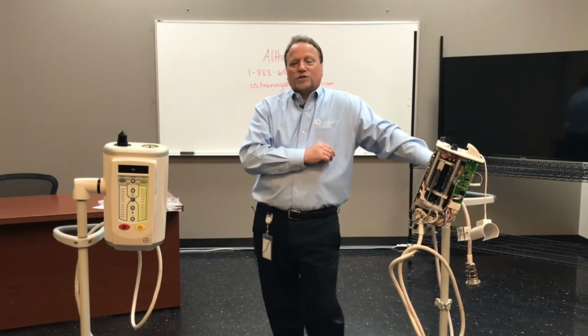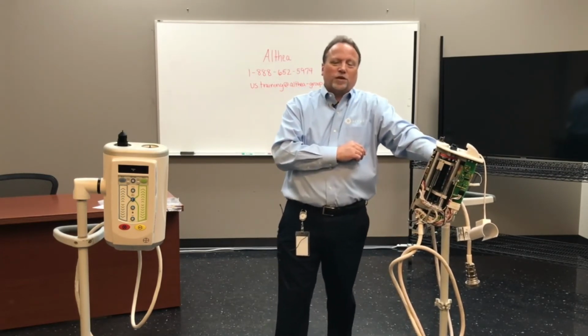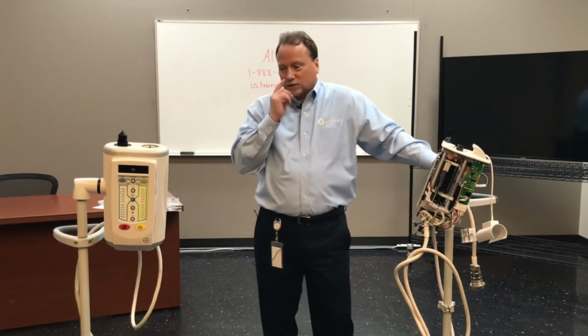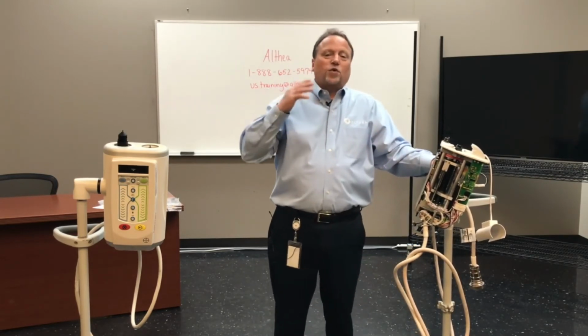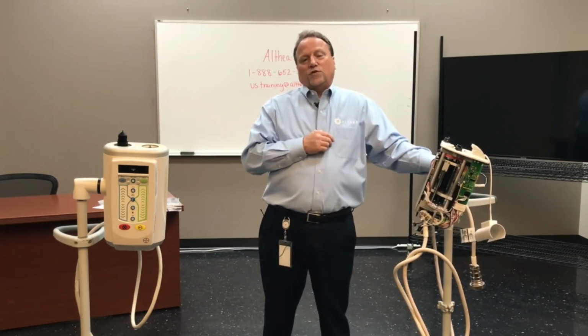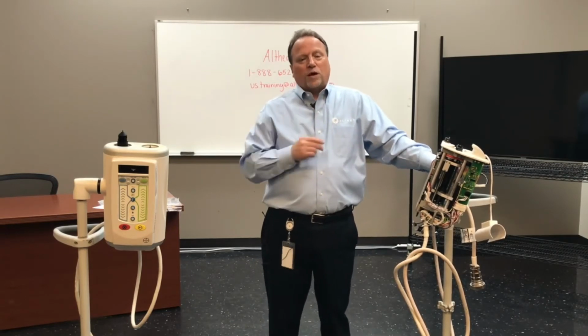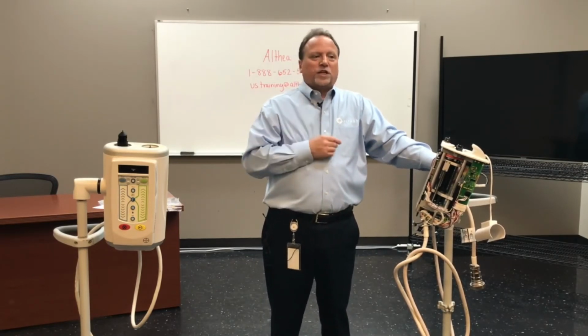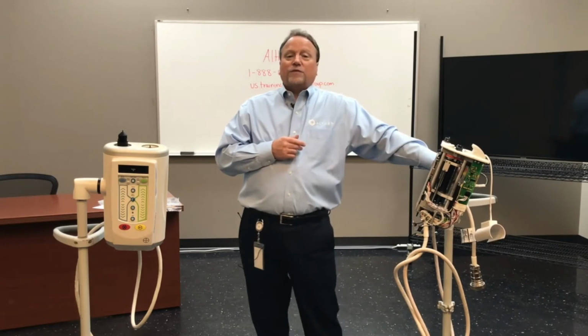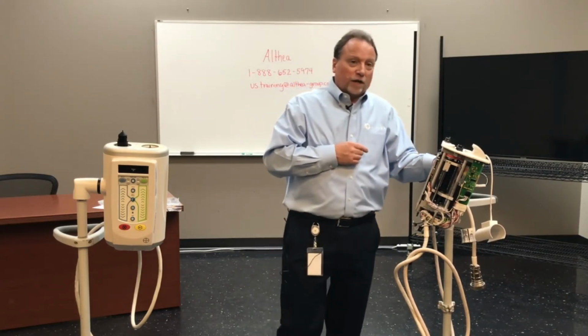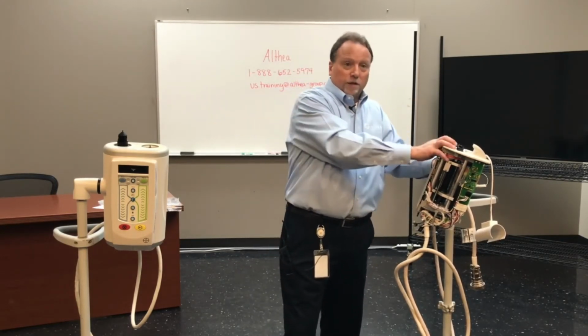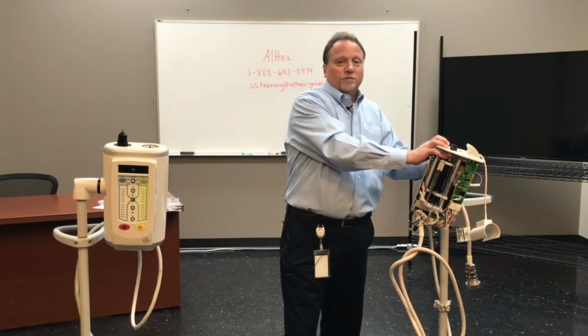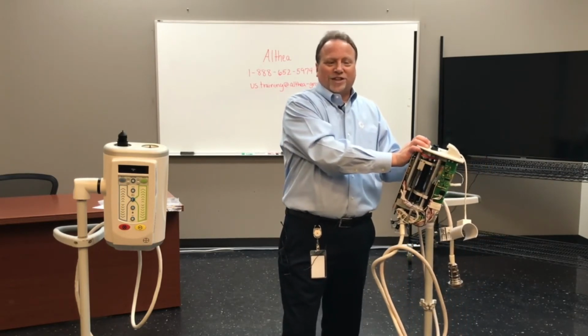Power supply voltages—we do check those. It's important to have the right voltage. Like on the Stellant, you need a constant 48 volts; if your voltage is fluctuating, it's going to give you problems, so we need to check that voltage. DAC voltages, digital to analog or analog to digital—again on the Provis, older technology, need to check that stuff out.